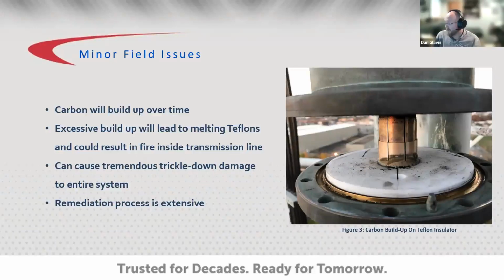So the major issue in RF system failures is that when an issue occurs and it's investigated, the culprit has already typically gone up in smoke. It's burnt and turns into soot and falls down. Gravity helps to pull it down. So it's tough to find the original place of a failure inside a transmission line system.